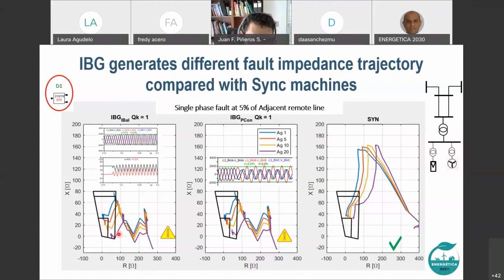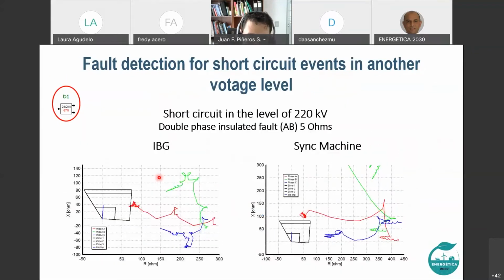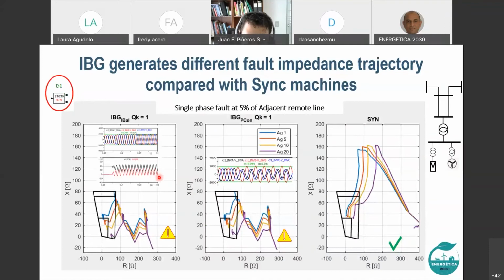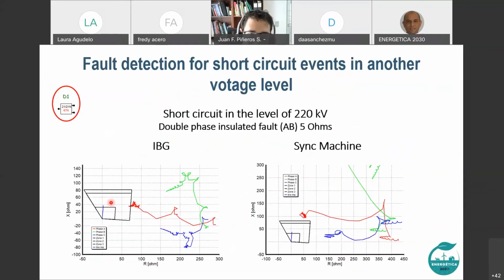And of course, some incursions we will have, and this is a problem. We were testing with a current balance control mode, and as well a constant active power control mode. We observe the same behavior, and this is very important. Then the performance will be different. We were talking before about a single phase to ground fault in the adjacent line. This is very important because we are not having any fault in this case at the protected line, and then we are tripping for an external fault. It's very important.